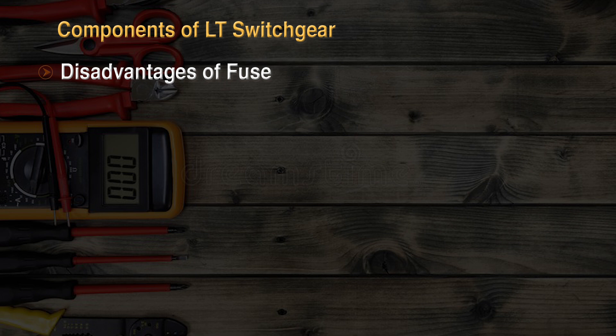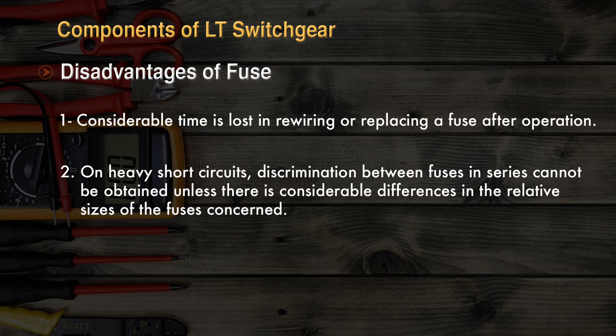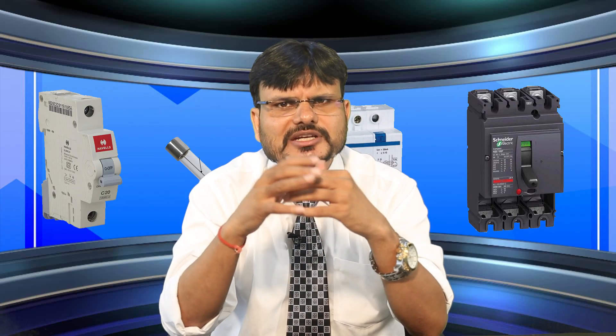The disadvantages of a fuse are: considerable time is lost in rewiring or replacing a fuse after operation; on heavy short circuit, discrimination between fuses in series cannot be obtained unless there is a considerable difference in the relative size of the fuses concerned; and the current-time characteristic of the fuse cannot always be correlated with that of the protective device.